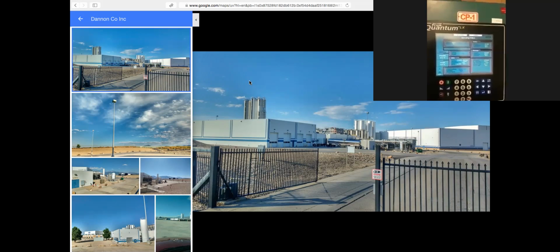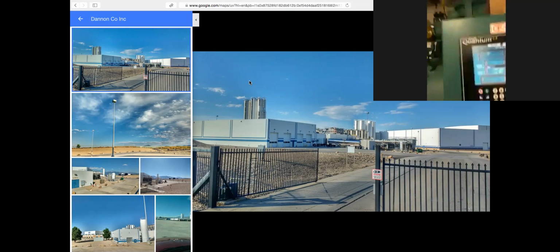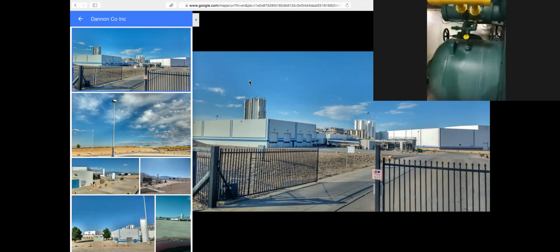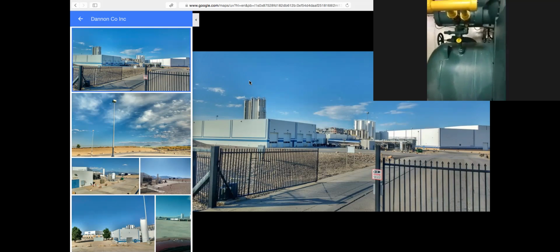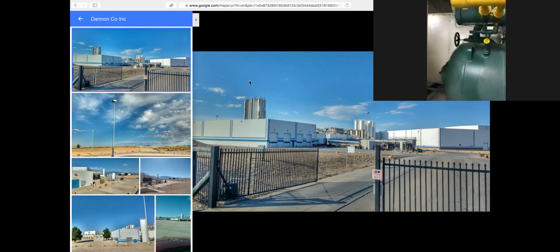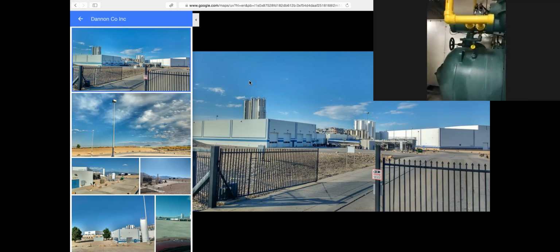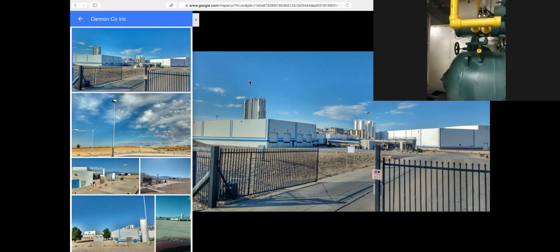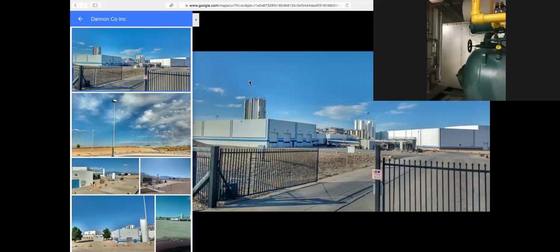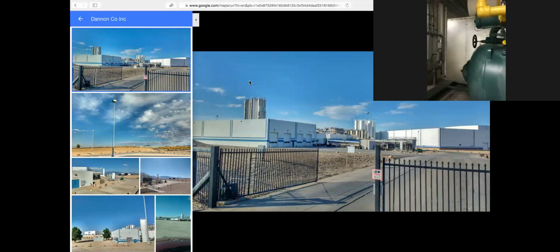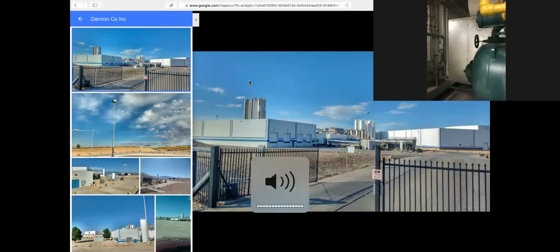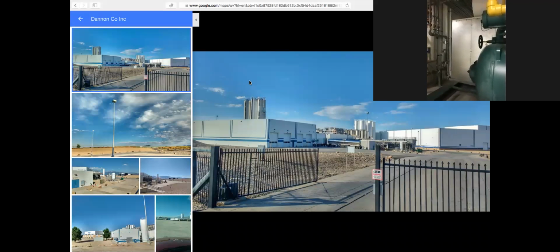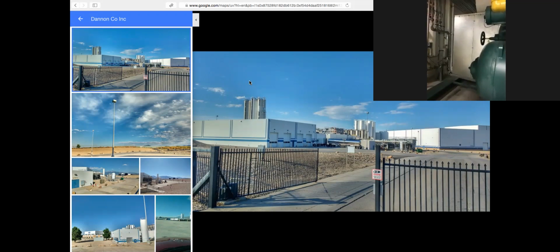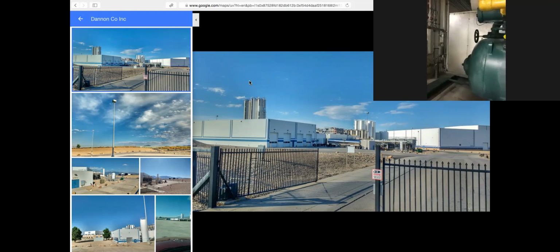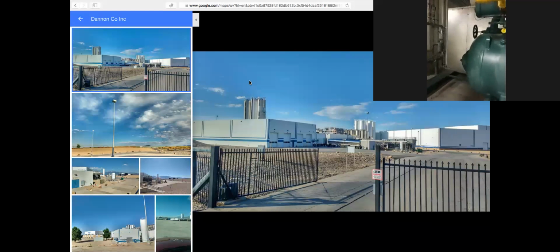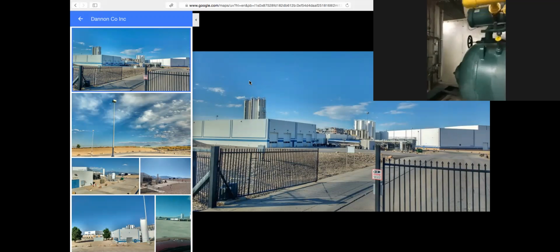Once it leaves this, it goes to that heat exchanger and through a temperature sensor. By the time it gets to that chiller, it is warmed up to about 22 to 23 degrees, and it starts going over to that chiller that we were at yesterday. So for us to get a reading of 19.8, 19.9 degrees yesterday is a very difficult thing to do, shoving that glycol 1,000 feet.